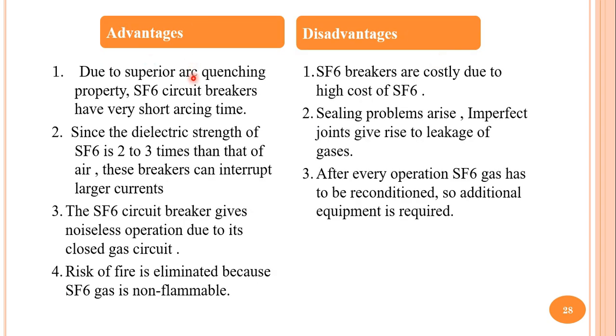The main advantages of SF6 circuit breakers are: due to the arc quenching property of SF6, operating time is very less; since the dielectric strength of SF6 is 2 to 3 times that of air, these breakers can interrupt large currents; SF6 circuit breakers give noiseless operation due to a closed gas circuit; and risk of fire is eliminated because SF6 gas is non-flammable. The main disadvantages are that it is costly due to the high cost of SF6, sealing problems arise as imperfect joints give rise to gas leakage requiring tight shielding, and after every operation the used gas has to be reconditioned, requiring additional equipment.